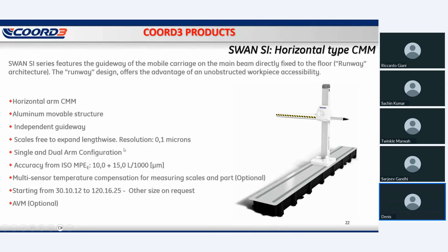Also, the machine can be equipped with multi-sensor and temperature compensation. The machine can be in single and dual arm configuration. The scale free to expand, 0.1 micron. About the size, starting from 30, 10, 12 to 120, 16, 25. Other sizes on request. Also, this machine can be equipped with the anti-vibration system. Jupiter is the biggest horizontal arm that we do. The structure is always in aluminum. The difference is that the Jupiter is covered, and we can reach bigger dimensions with respect to the Swan.